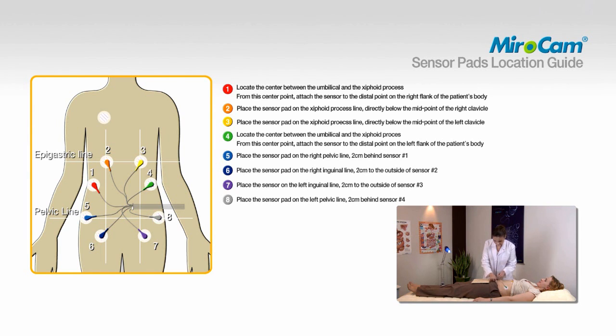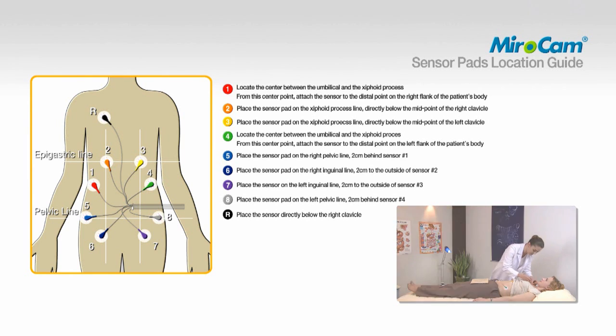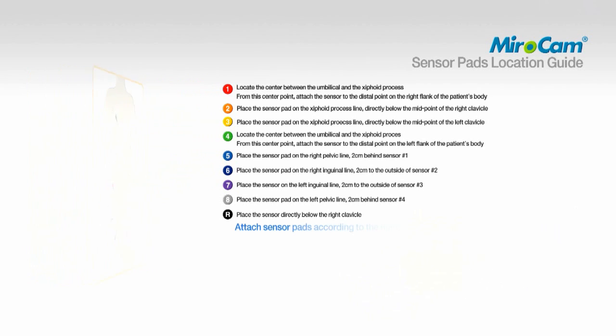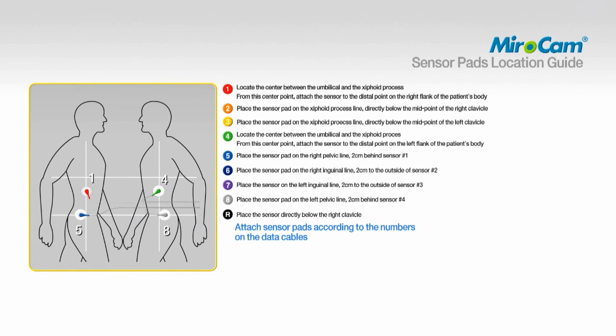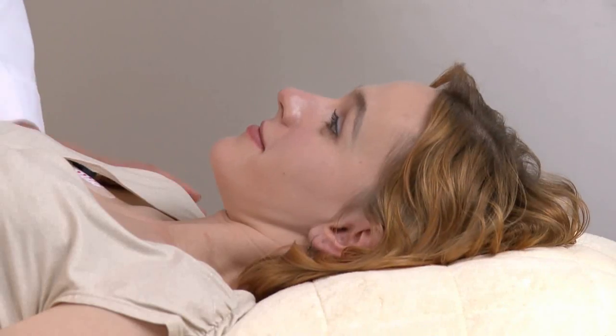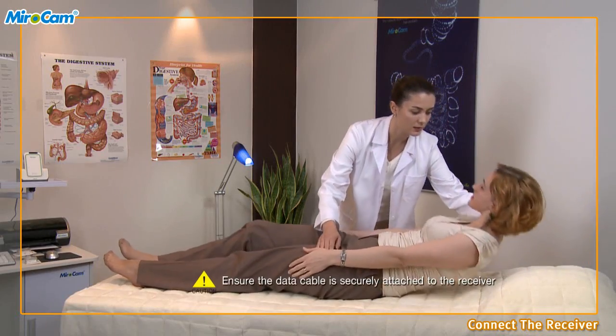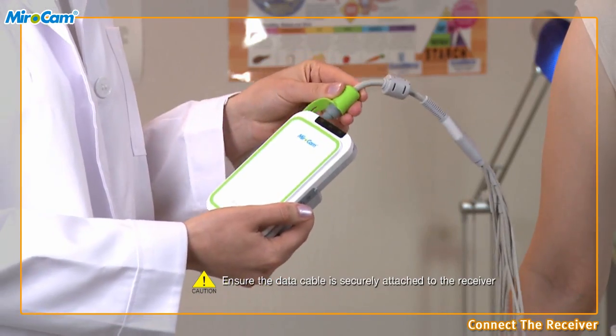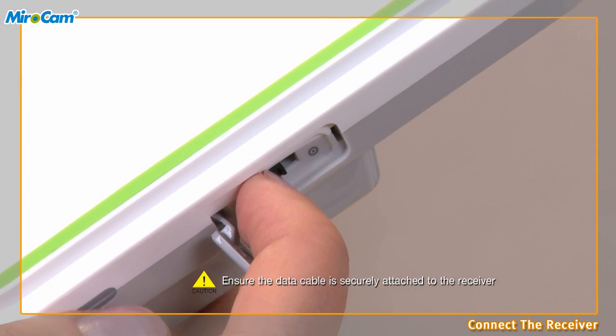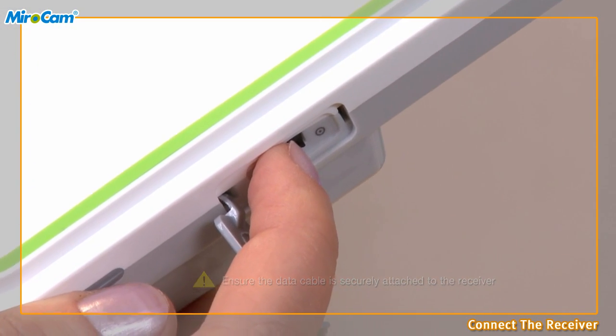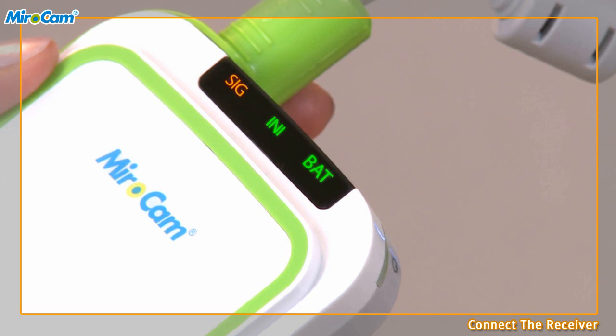To attach pad number 8, place the sensor pad on the left pelvic line, 2 centimeters behind sensor number 4. To attach pad R, place the sensor directly below the right clavicle. The numbering of the data cables and sensor pad placement must match the specified area. Connect the receiver. After attaching the sensor pads, have the patient sit up and connect the data cables to the receiver. Turn on the receiver and check the battery indicator. The SIG indicator should be orange, and the INI and BAT indicator on the receiver should be green.